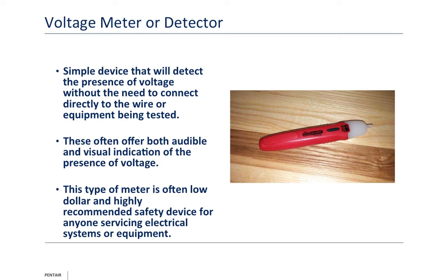When I was training to be an electrician, we were taught one hand in pocket, no shocky. Which literally meant you put one hand in your pocket, or we were taught to reach behind to your utility belt and grab it, and then with the back of your hand touch the electrical device to see if it's on. The reason is, if you grab it with the palm of your hand and latch onto the equipment, your natural instinct is to try to grab that hand and free it with the other. By doing that, you create a circuit across your heart and you could very well die. So that's where we're at. First and foremost, don't be touching electrical wires. If you must, do it with the back of your hand, but don't touch electrical wires.